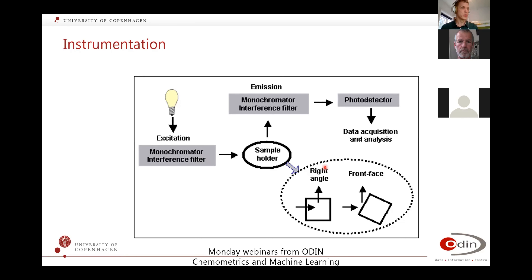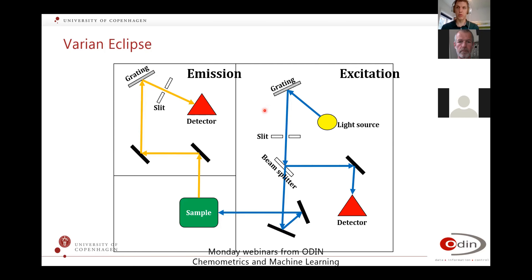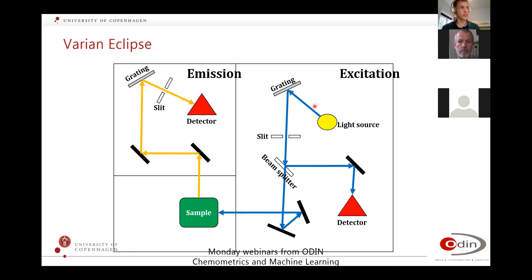How does the instrument look? A typical fluorescence instrument has one side for excitation, then a sample, and then emission on the other side. That signal reaches the red detector, which is what you read off at the computer. The instrument contains a light source — a xenon lamp — then a grating, which is a mirror that turns slowly. Depending on the angle of this mirror, the light goes further into the instrument through a beam splitter and hits the sample at a very specific wavelength determined by the grating.